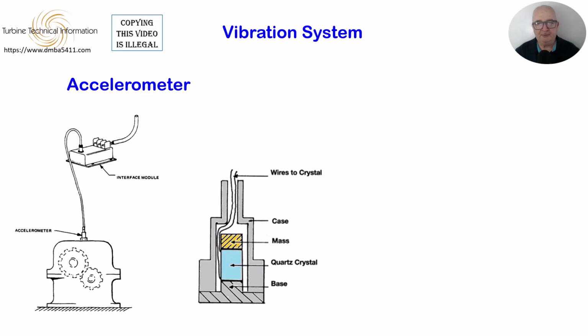The accelerometer uses a piezoelectric crystal sandwiched between the base of the sensor and an internal mass weight. When the crystal is compressed between the base and the mass weight, an electric charge is generated that is proportional to the applied force of the vibration. This sensor is normally used on the epicyclic reduction gearboxes used on generator sets, as these gearboxes have high frequencies.